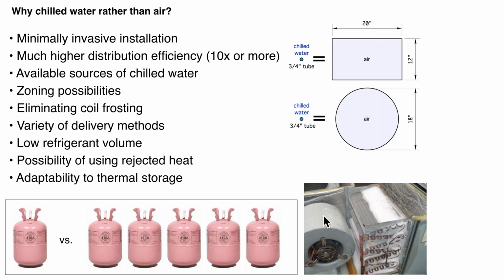Coil frosting: when you're working with a direct expansion coil, a coil that has refrigerant going through it, if the refrigerant charge gets low, it's possible to frost over the coil. Typically, when you see this, you know you've got a low refrigerant situation, or it could be something with the TXV and so forth. That's not going to happen with a hydronic coil. It simply doesn't get cold enough to cause that frost to happen. Low refrigerant volume. Again, this is just a graphic to illustrate when we're dealing with either a ductless mini split or commercially a VRF system, we're dealing with much, much greater volumes of refrigerant.